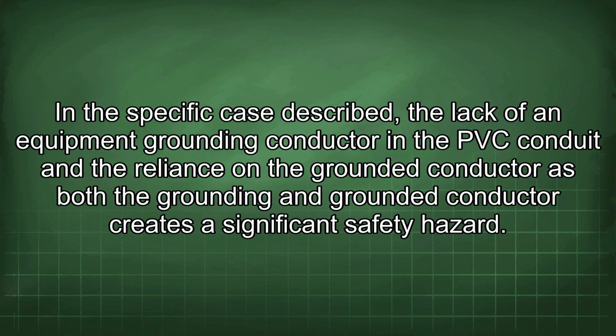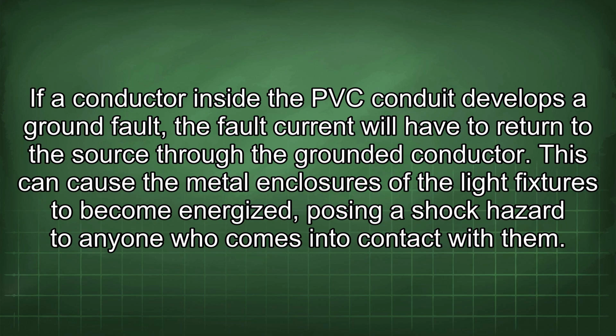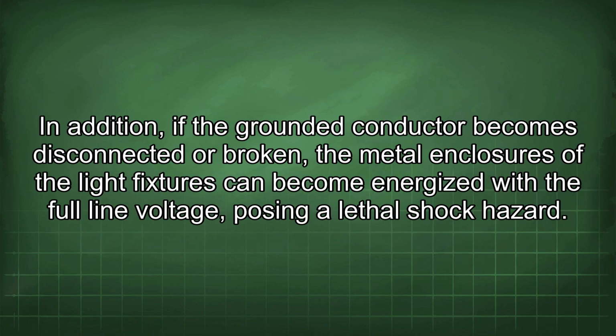In the specific case described, the lack of an equipment grounding conductor in the PVC conduit and the reliance on the grounded conductor as both the grounding and grounded conductor creates a significant safety hazard. If a conductor inside the PVC conduit develops a ground fault, the fault current will have to return to the source through the grounded conductor. This can cause the metal enclosures of the light fixtures to become energized, posing a shock hazard to anyone who comes into contact with them. In addition, if the grounded conductor becomes disconnected or broken, the metal enclosures of the light fixtures can become energized with full line voltage, posing a lethal shock hazard.